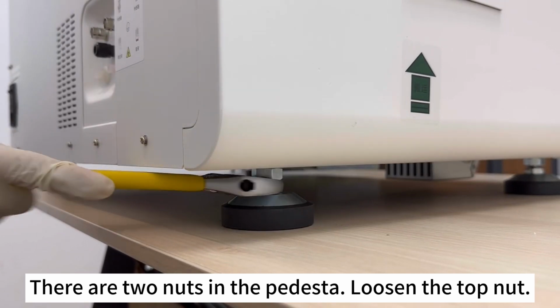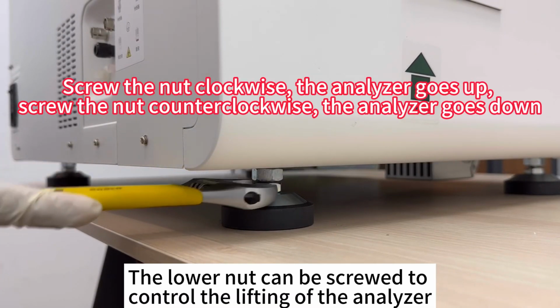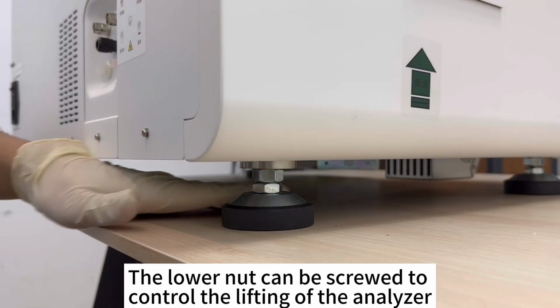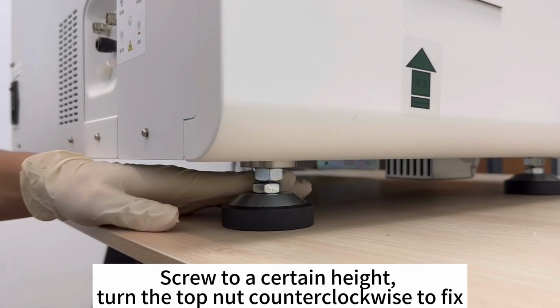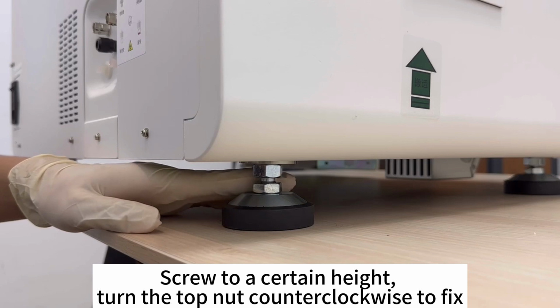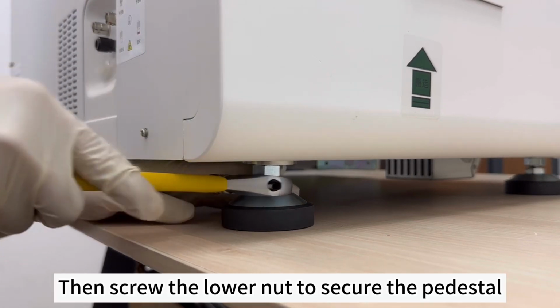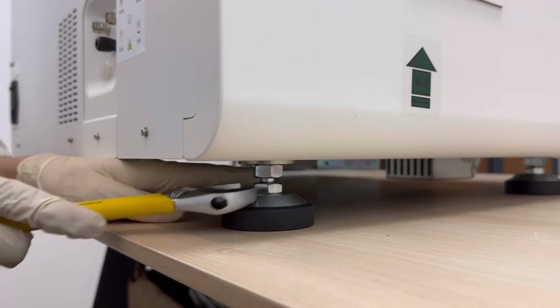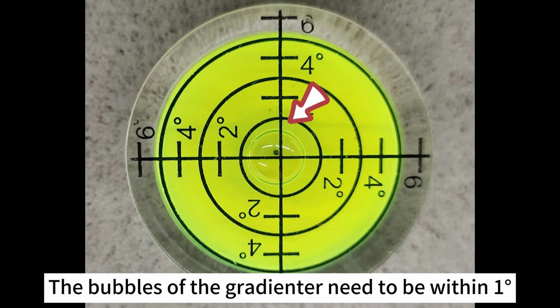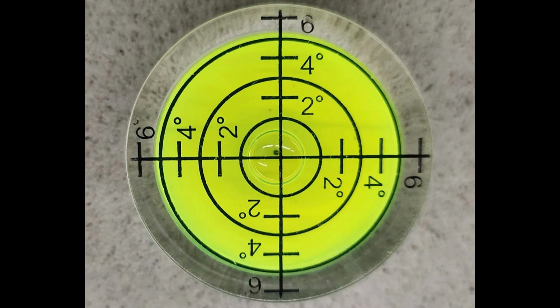Loosen the top nut. The lower nut can be screwed to control the lifting of the analyzer. Screw to a certain height, turn the top nut counterclockwise to fix, then screw the lower nut to secure the pedestal. The bubbles of the gradienter need to be within 1 degree.